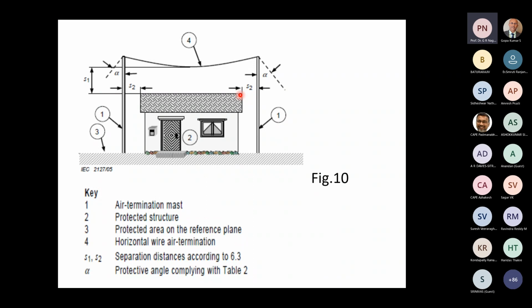As I mentioned to you several times, all these methods are based on statistical field experience. Whether it's the geometric method or the rolling sphere technique, they are dependent upon field experience. In the rolling sphere technique, it's a striking distance concept where the constants K and N of that equation, if you remember, are subject to large variations. Therefore, we cannot say it's absolutely 100% foolproof. So for things which are very, very dangerous, we must protect them so that no chance of lightning failure can occur there. We have to provide an isolated system.